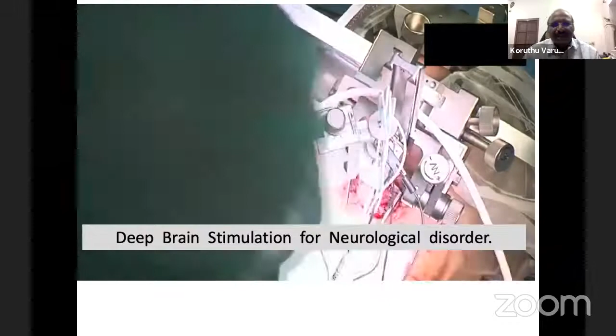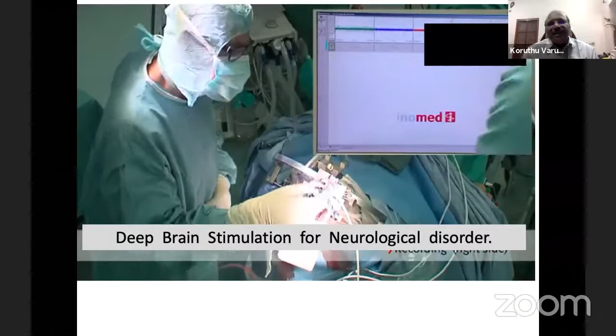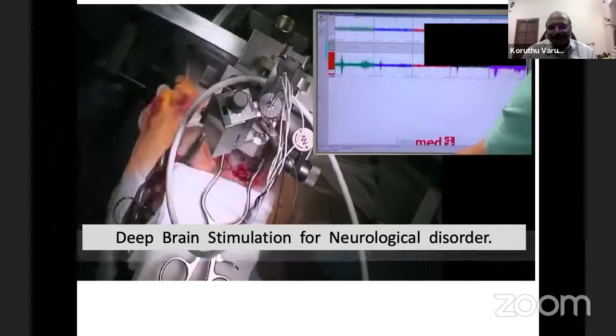Now, nothing else. Doctors are free. You have to give stimulation. Switch on the machine and see whether it is stimulating. Slightly adjust the voltage or area, up and down. Okay, start firing. See, the signal is already coming. It is exactly that area that is given. And now you have to calibrate it. Even though the signal is given, we have to see the patient.